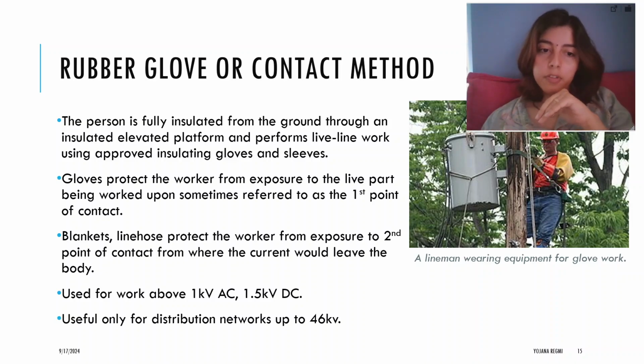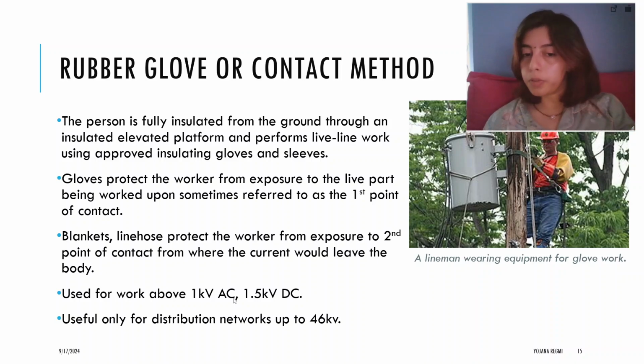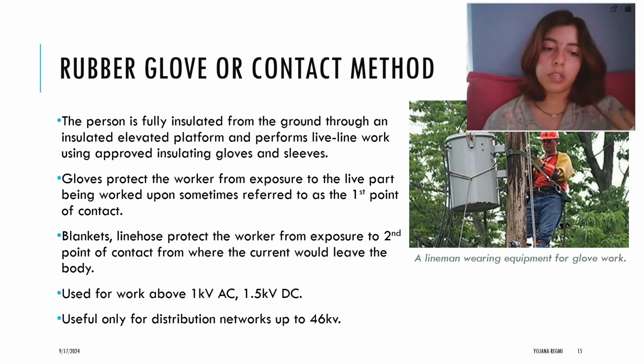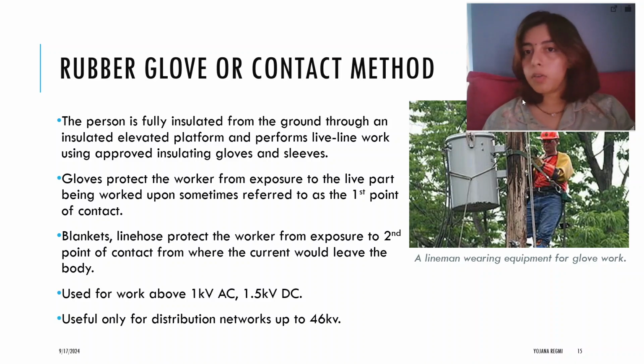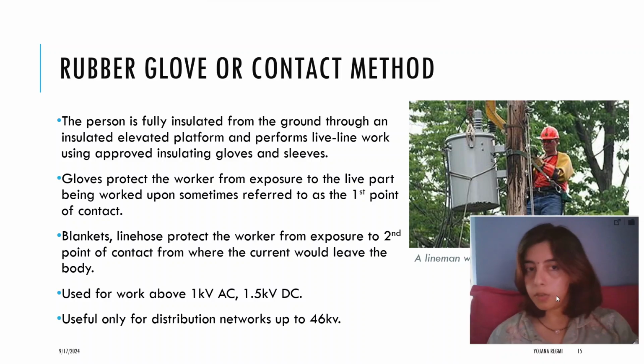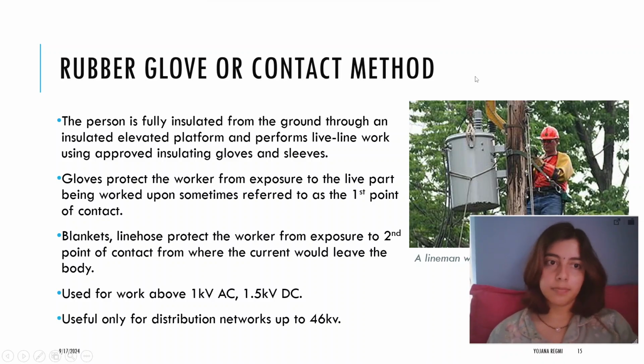The second point of contact is the blankets and line hose that the worker uses, so that even if current is passing through him, it will not leave the body - because if current leaves through the body, the circuit is complete and the person gets shocked. This is avoided by use of blankets and line hose. This method is used for work above 1 kilovolt AC and 1.5 kilovolt DC, and is useful only for distribution networks up to 46 kilovolts. In Nepal, we don't have 46 kilovolt distribution lines, FYI.